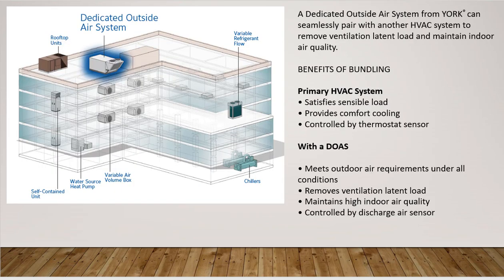In buildings that use zone-level terminal units for cooling and heating, such as VRF, water source heat pumps, fan coils, small DX split systems, chilled beams, or sensible cooling terminal units, a separate dedicated outdoor air system is often used to provide ventilation. The DOAS unit seamlessly pairs with another HVAC system to remove ventilation latent load and maintain indoor air quality.